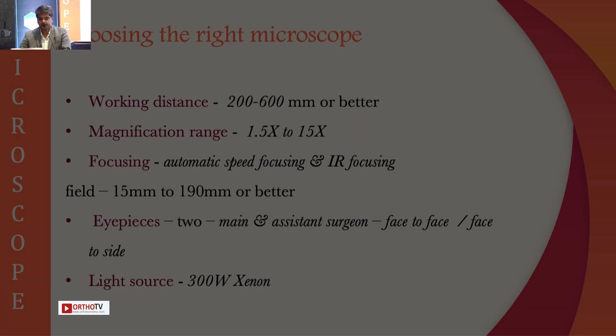The working distance should be around 200 to 600 millimeters, with a magnification range of 1.5 to 15x. Both should be motorized, automated, and the control should be on the hand grip. Focusing should be either automated or through the eye, with a field of 15 to 190 millimeters. Eyepiece: always buy one which has two, one for you and one for the assistant, because spine surgeries go with one main surgeon and your colleague assisting. So face to face is always better.